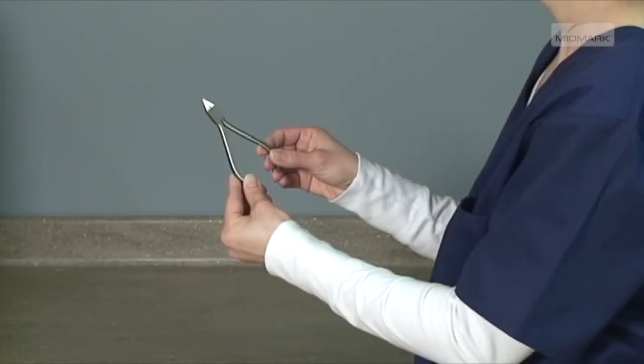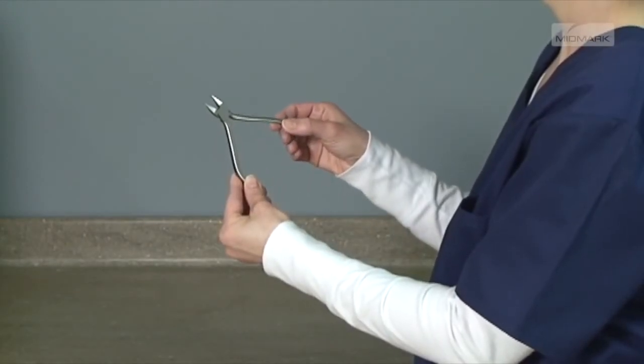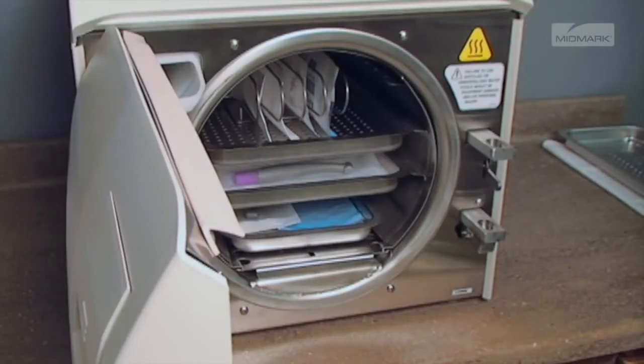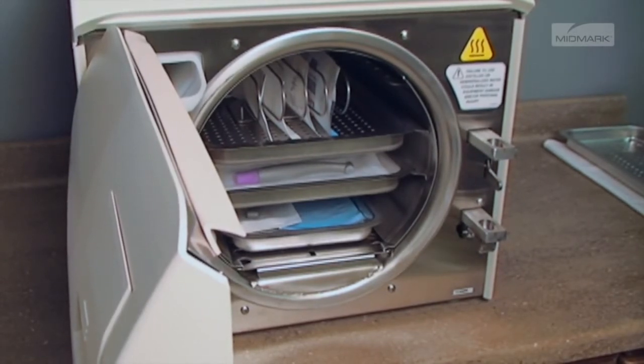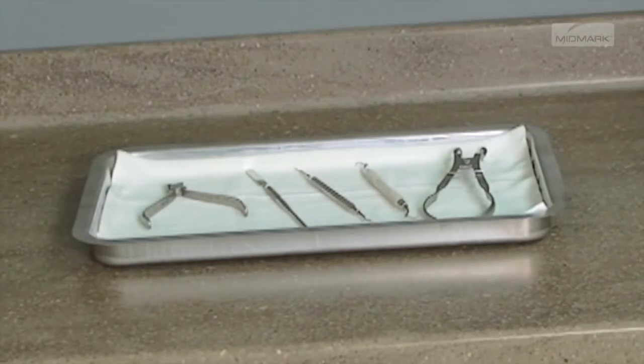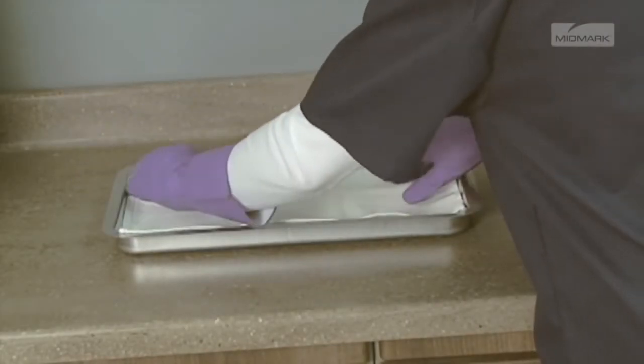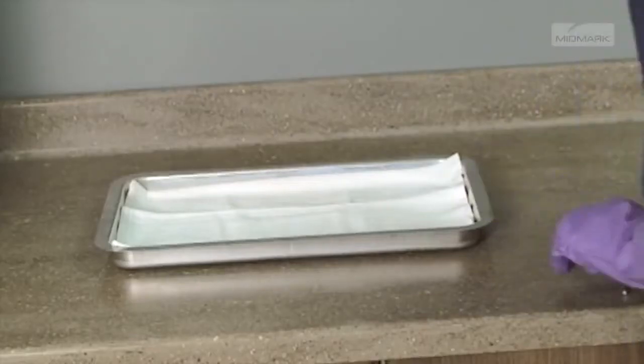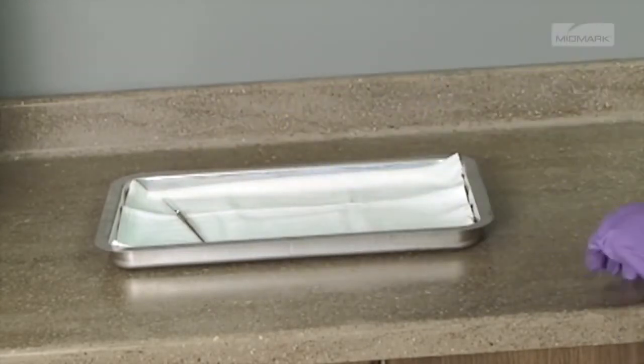Using other trays could restrict air and steam flow to items. Place jointed items, like forceps or pliers, in an open position. Handpieces and instruments must be single-height loaded, not piled or stacked. The M9 and M11 are capable of sterilizing unwrapped instruments for immediate use. Place a towel or absorbent paper on the bottom of the tray before putting unwrapped items in the tray. Follow regulatory guidelines for using unwrapped, sterilized instruments.